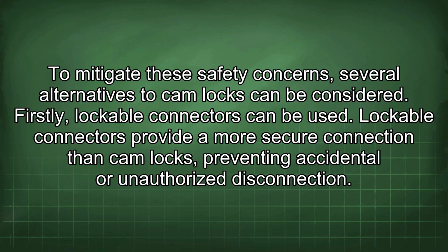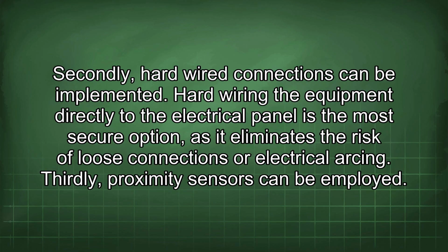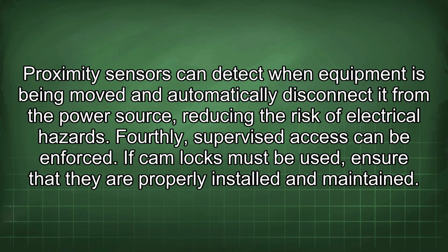Firstly, lockable connectors can be used. Lockable connectors provide a more secure connection than cam locks, preventing accidental or unauthorized disconnection. Secondly, hardwired connections can be implemented. Hardwiring the equipment directly to the electrical panel is the most secure option, as it eliminates the risk of loose connections or electrical arcing. Thirdly, proximity sensors can be employed. Proximity sensors can detect when equipment is being moved and automatically disconnect it from the power source, reducing the risk of electrical hazards. Fourthly, supervised access can be enforced.